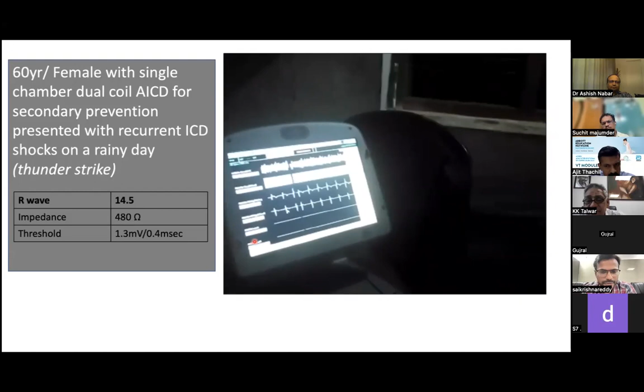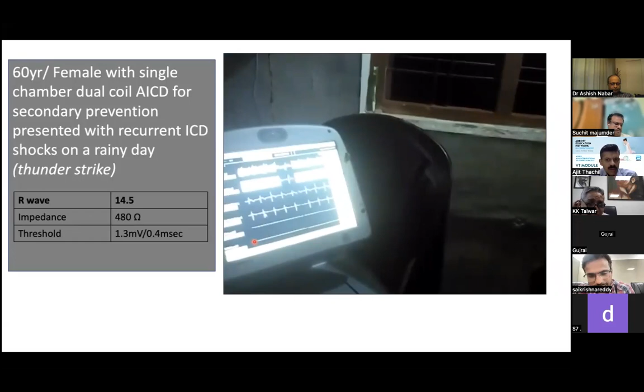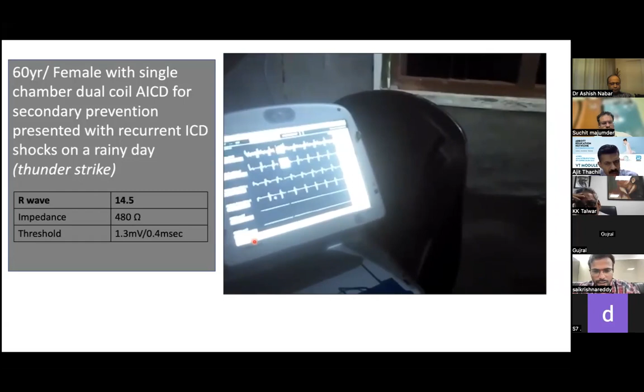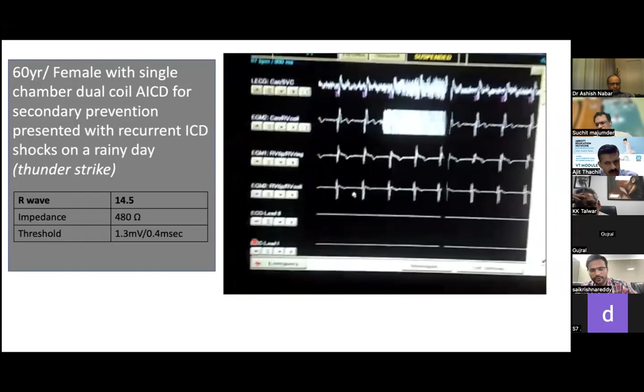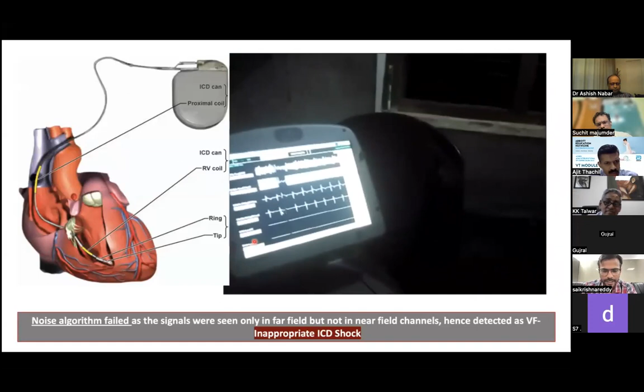As I already discussed, for the ICD to label it as noise and halt the therapy, it should be seen in all the channels. The problem here is that though it was EMI, because it was not seen in all the channels, it gave a shock, which was inappropriate. The reason it was not seen in the bipolar near field is probably that grounding was not good and the grounding current was very minimal, only being picked up by the far field signals. So this was an inappropriate shock for EMI.